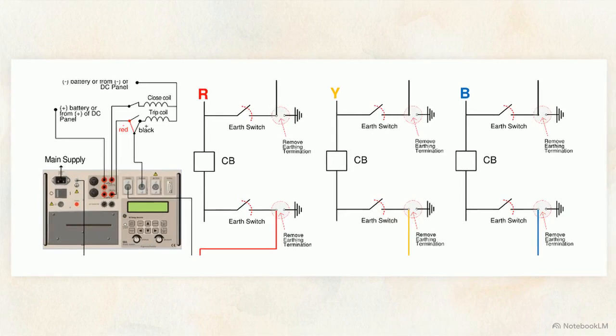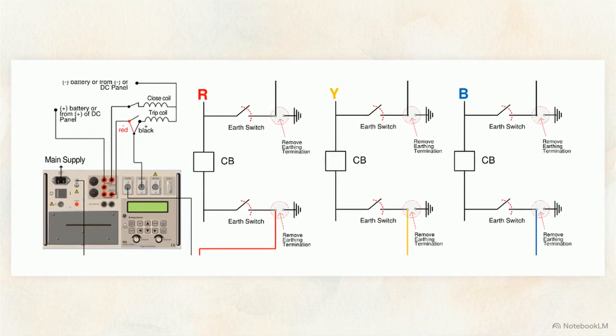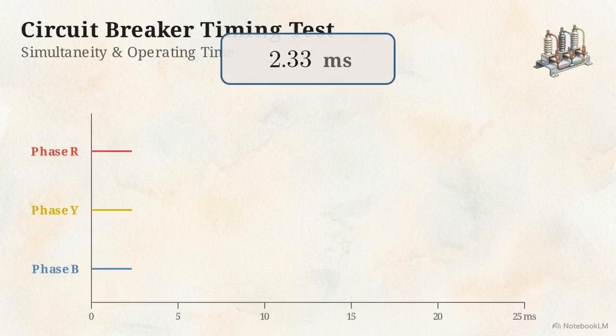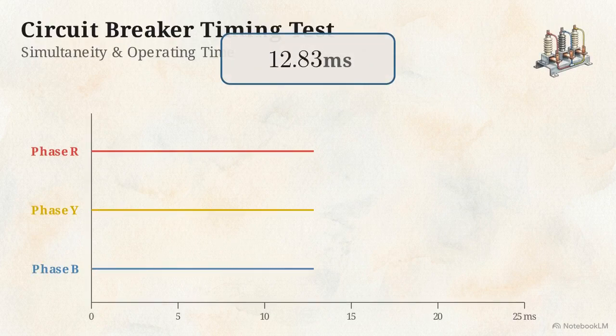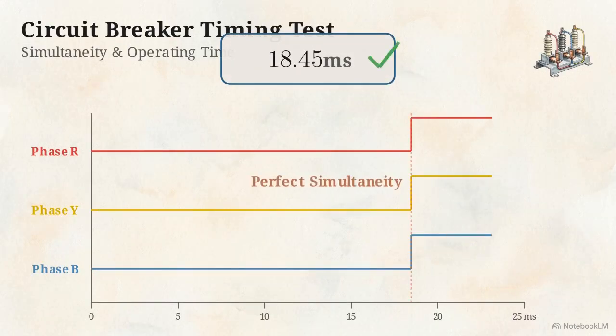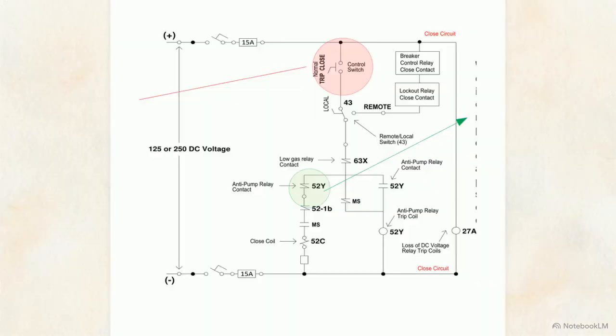This diagram shows how the circuit breaker analyzer maps its channels to the close coil, trip coil, and main phase timing points to measure millisecond response times. The operating time for both open and close commands must register under 20 milliseconds, with simultaneity across all poles to prevent phase imbalances. This schematic details the anti-pump relay circuit, preventing continuous cycling during a fault.